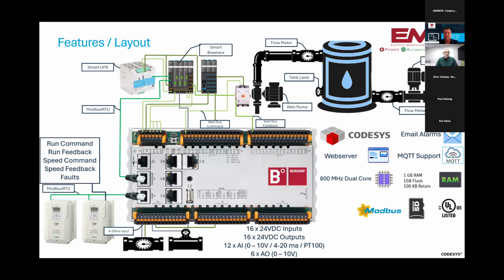And then you see the tank there, and you've got your pumps, your well pumps or valves filling that tank. Those are normally hardwired to outputs or inputs on the PLC. But we also, as we'll show, have some that we can run over Modbus. So in some situations, the wells are remote from the tank site. And in that situation, they're able to run Modbus TCP over a standard radio connection and be able to control up to 3 wells for filling that tank.